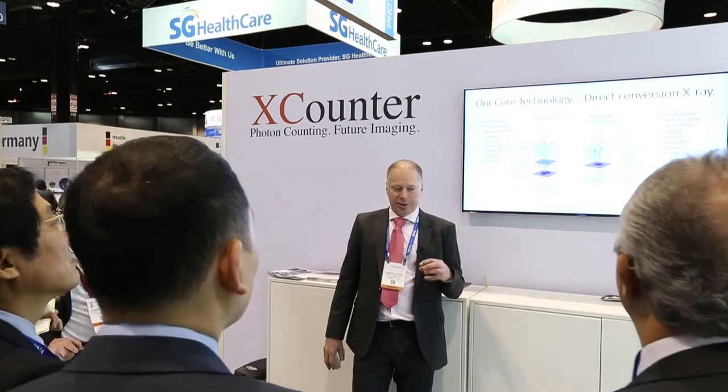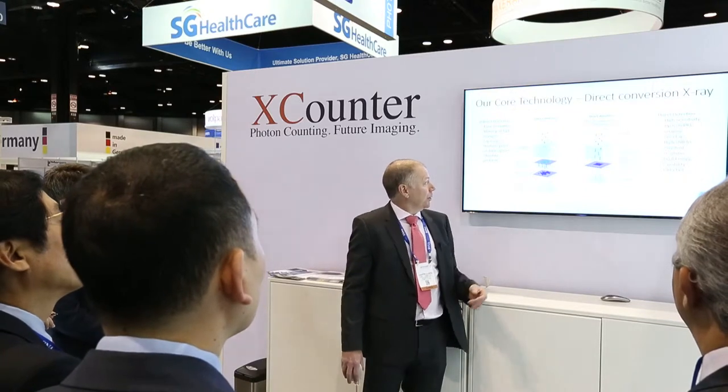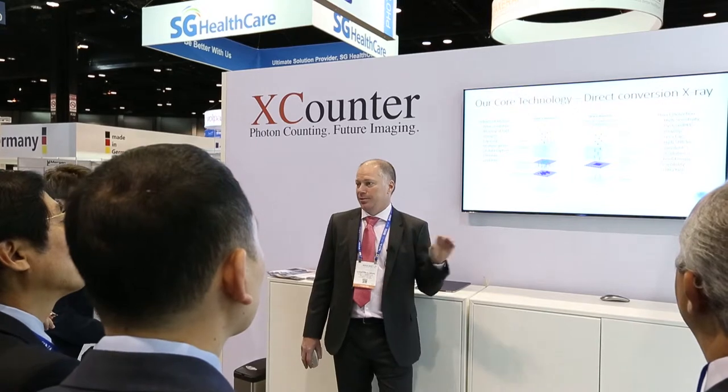The core technology is that we are directly converting the X-rays into charge. We are using a semiconductor — in our case CdTe or CZT — to directly convert the X-rays into electrical signals that we can detect. In comparison to scintillating devices, we are using one step less and we don't get the blurring from the scintillator.